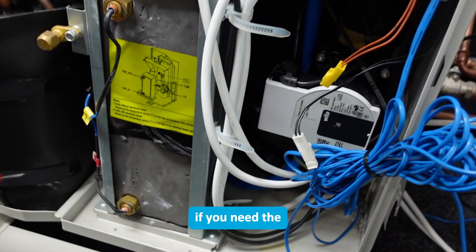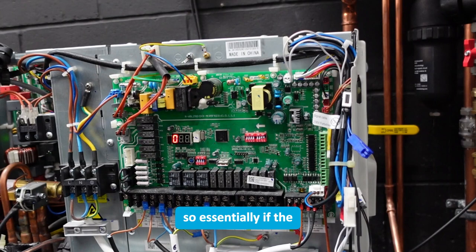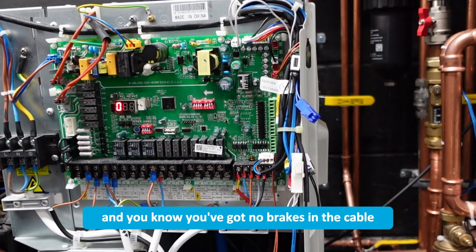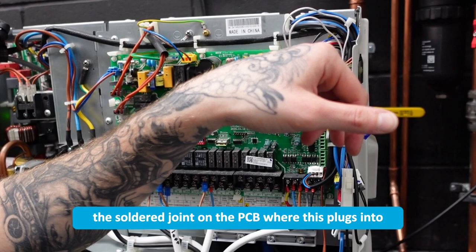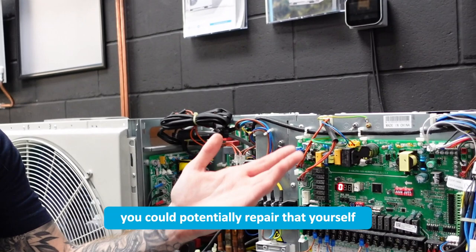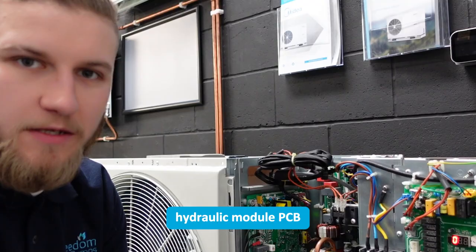So we know the probe end of our sensor is fine. If you need the full resistance characteristics chart of that sensor, let us know and we'll be happy to send it over. If the resistance reading is in range, you've got good connection at both ends, and no breaks in the cable all the way up to the cylinder, then it's possible that the soldered joint on the PCB where this plugs in might be cracked or partially broken. If you're skilled with a soldering iron you could potentially repair that yourself, otherwise it would be a case of getting a new hydraulic module PCB.